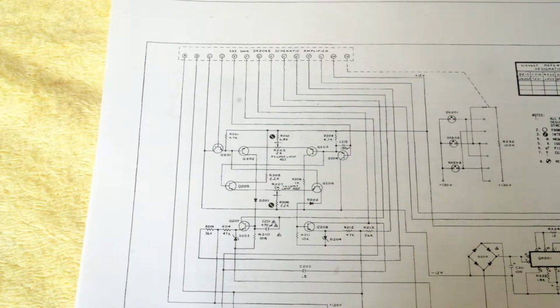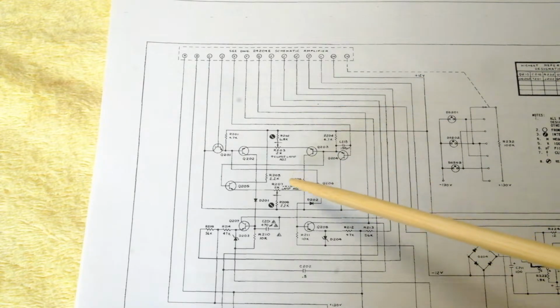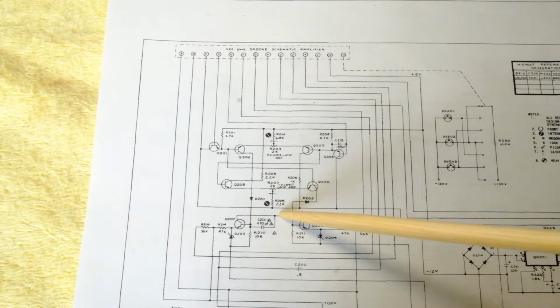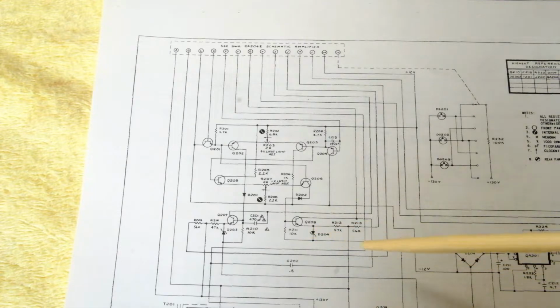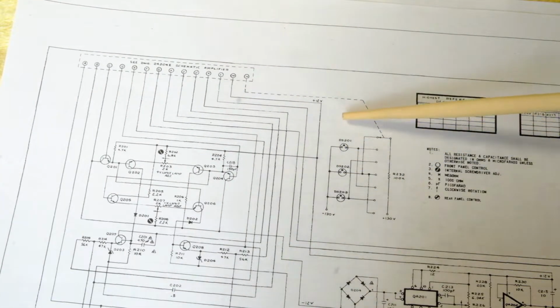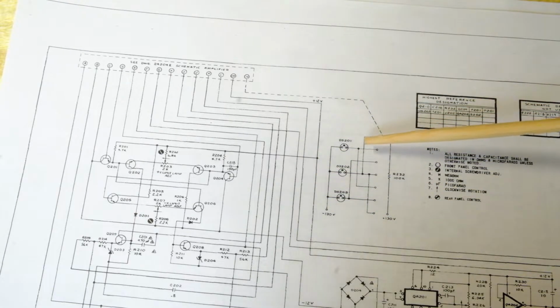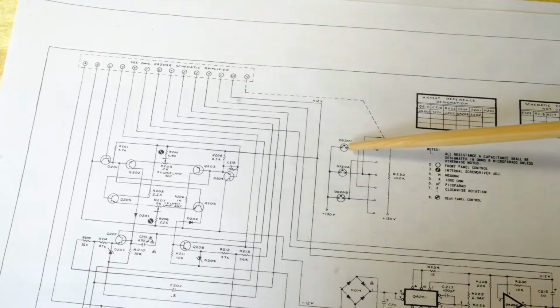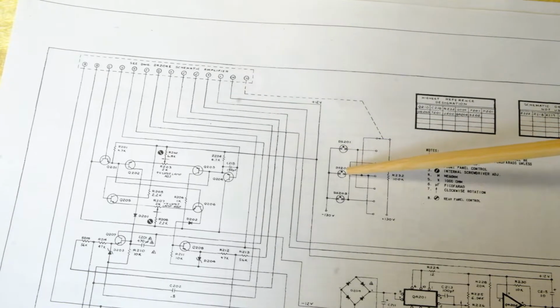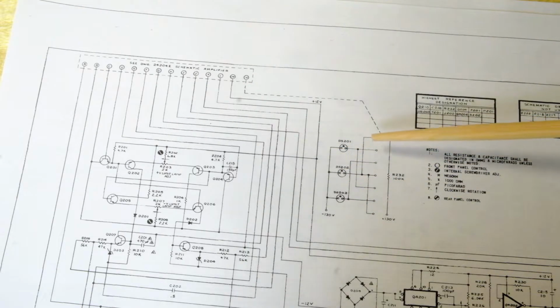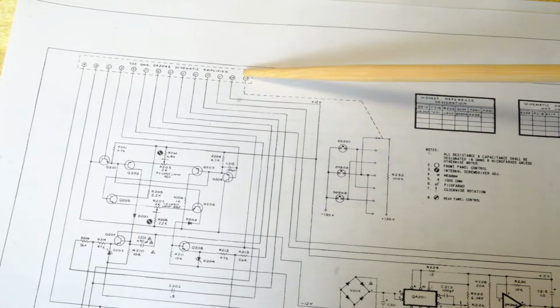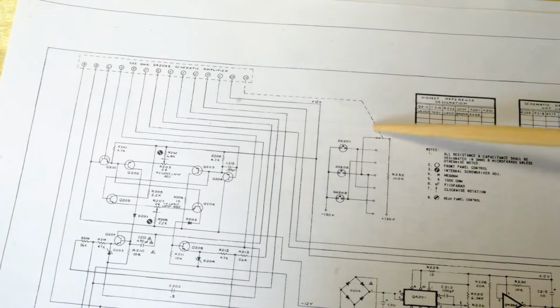That is, if the voltage exceeds a certain value, then a light will show up on the front panel saying that you have reached the compliance limit, either positive or negative, and they are both here. And that is useful to know if you're checking what's happening with the instrument, and whether it's trying to drive too high a voltage or so. The three neon lamps on the right side are for the decade settings. So depending on whether it's 10 milliamps or 1 milliamp or 100 microamps, 10 microamps, different lights are lit by this. And this is again controlled by a switch on the main board, and these are all ganged together, and it's shown on this particular schematic.